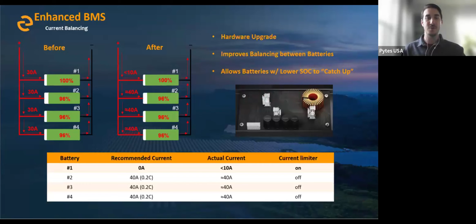What this current limiter component does, which is something on the hardware side inside the battery, is allow those lower batteries to continue taking on more charge, while the higher one, essentially, increases its resistance so that it can't take as much current, and it lets the lower batteries catch up, if you will. So it's something we've incorporated here to improve the balancing between multiple parallel connected batteries, and at the end of the day lets the batteries with the lower state of charge catch up to the higher ones, if you will.